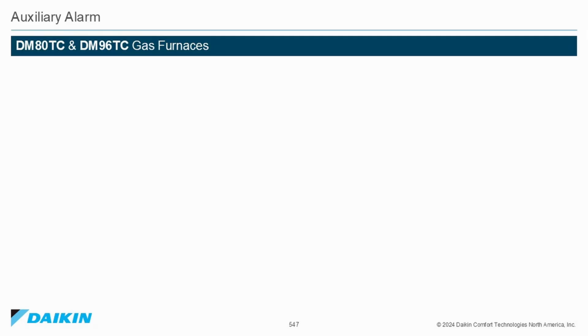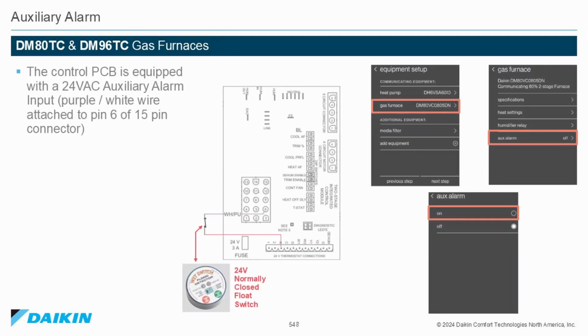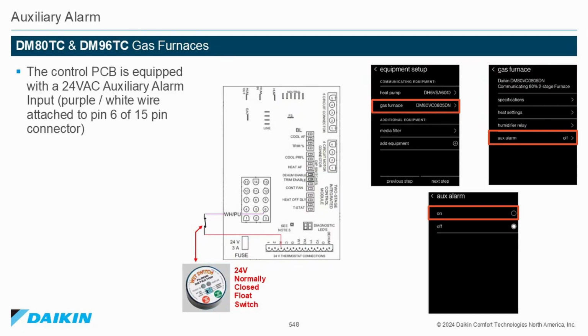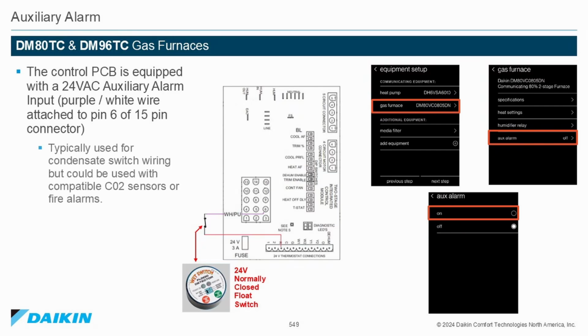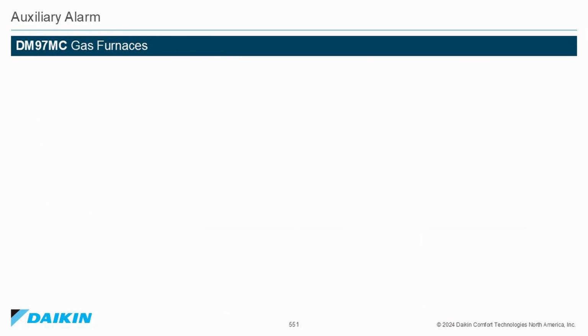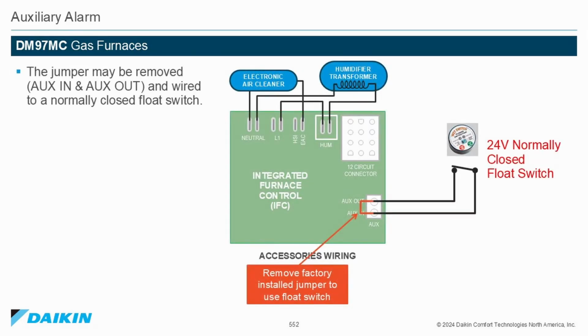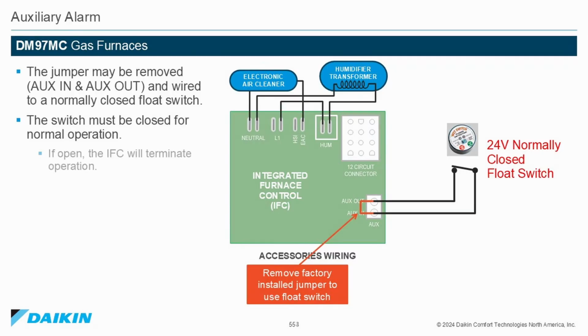DM80TC and DM96TC gas furnaces. The control printed circuit board is equipped with 24-volt auxiliary alarm input, the purple and white wire attached to pin 6 of the 15-pin connector. It's typically used for condensate switch wiring, but could be used with compatible CO2 sensors or fire alarms. Can be activated or deactivated from the thermostat. On the DM97MC gas furnaces, the jumper may be removed between auxiliary in and auxiliary out and wired to a normally closed float switch. The switch must be closed for normal operation. If open, the integrated furnace control will terminate operation.